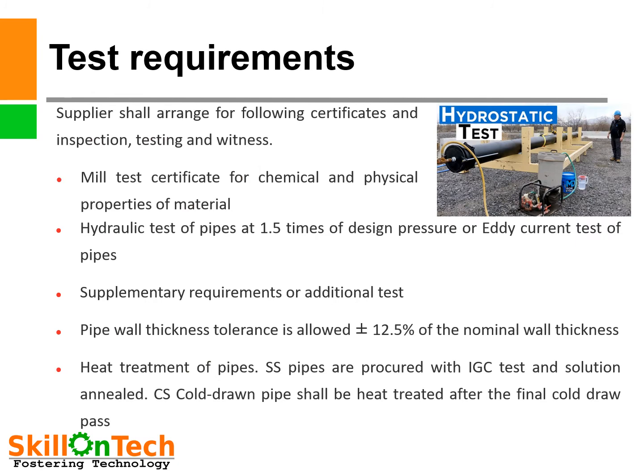Test requirements. We must specify the test requirements of the pipe. Suppliers shall arrange for the following certificates and inspection: mill test certificate for chemical and physical properties of material shall be obtained. Hydraulic test of pipes at 1.5 times design pressure, or eddy current test of pipes, shall be mentioned. Supplementary or additional tests wherever applicable shall also be mentioned. Pipe wall thickness tolerance is allowed up to ±12.5% of the nominal wall thickness. While purchasing a pipe, we can measure the thickness to check whether it is within tolerance or not. If a pipe is not within allowable tolerances, then it can be rejected.